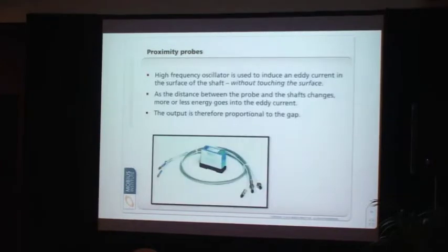We can say it's a certain distance from one probe to the shaft and the other probe to the shaft, and you can tell based on those relative distances just where it is. That's what our two proximity probes, normally mounted 90 degrees apart, give us, allowing triangulation. Sometimes for physical or design reasons they may not be exactly 90 degrees, but then the readings have to be compensated for. We'll keep it simple and use the case of 90 degrees.